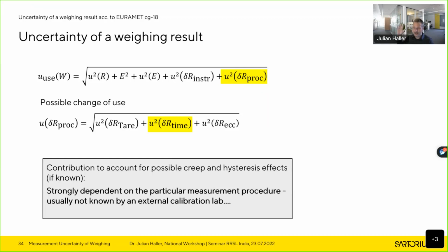But there's only one standard document giving acceptance limits, and that's OIML R76. And that is, again, only applicable to legal metrology instruments. So if you're outside of legal metrology, you do not have standard acceptance limits. Therefore, we recommend to users, please define your own specifications. Okay. Thank you, sir.